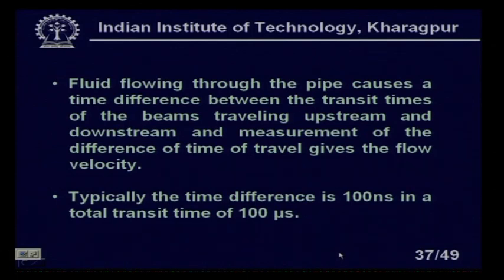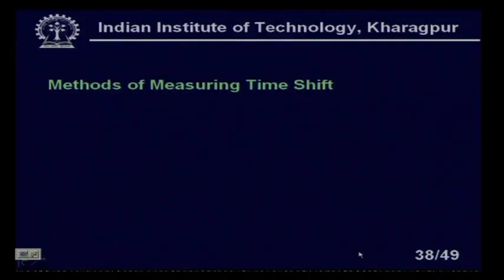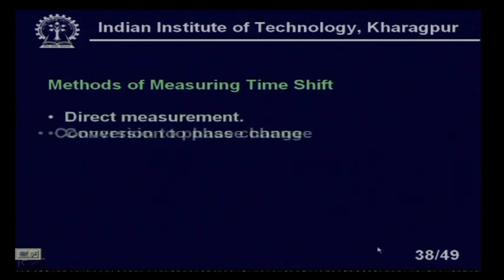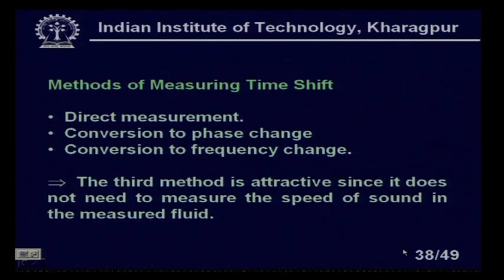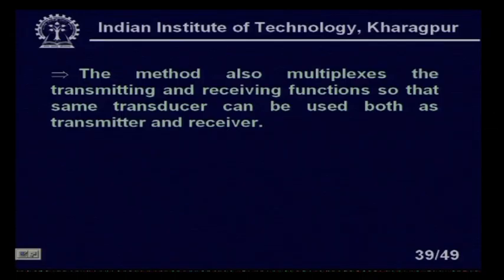Typically, the time difference is 100 nanoseconds in a total transit time of 100 microseconds. The accuracy of the measurement boils down to accurately measuring this 100 ns time difference. Methods for measuring the time shift include: direct measurement, conversion to a phase change, and conversion to a frequency change. The frequency change method is most attractive since it does not require knowing the speed of sound in the measured fluid.